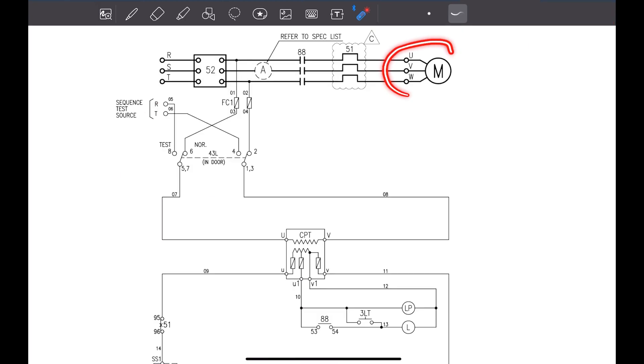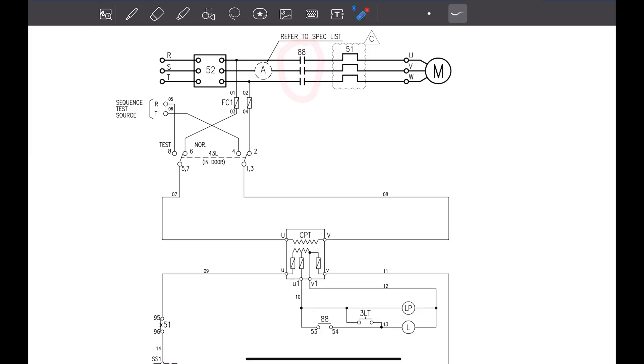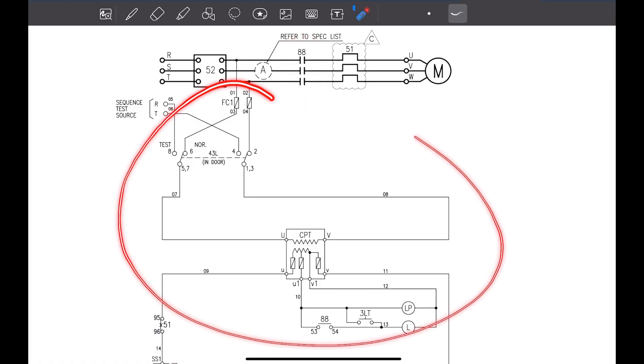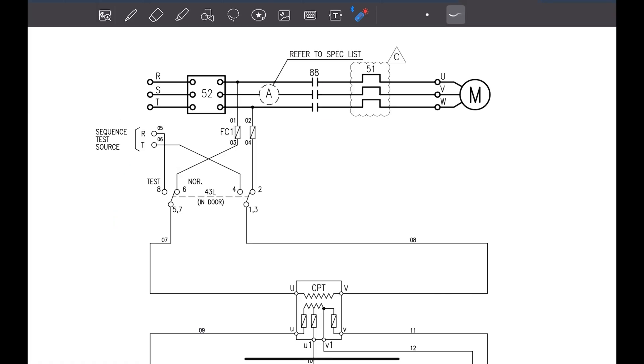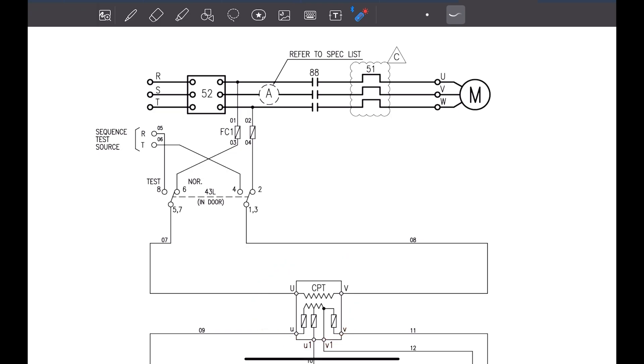Now this motor will only start when this 88 allows power to be transferred from this side to this side. Now we have to see when will the 88 get energized or when it will allow the power to be transferred from this side to this side. For that we need to come to the control side. As you can see for the control side there is two points taken from the R and T phase. Our motor is working on the three phase. But our control circuit it is working on the lower voltage either 220 or 110 depending upon the ship.